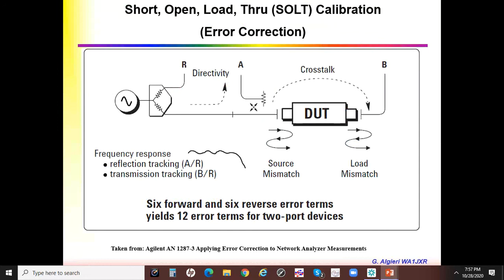And it does this for every frequency. As you sweep a network analyzer along, it sweeps from a start to a stop frequency, and it digitizes that sweep maybe into 1,000 points or 2,000 points. And for every frequency point, when you're doing the calibration, it stores error numbers for all these 12 terms. So it does the same thing for the other port, and then eventually you hook port 1 to port 2 of the network analyzer with a cable. You take the device under test out, you put a cable, and that's the through connection. And it crunches all of that, and it saves all that data into what's called a calibration file.